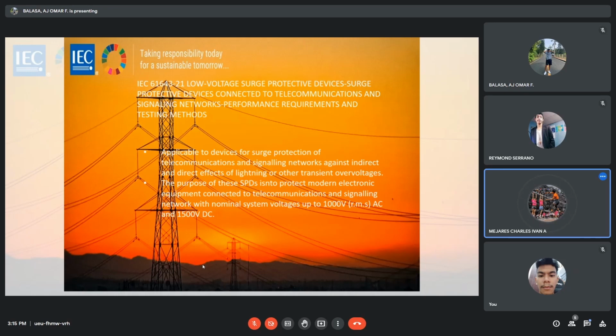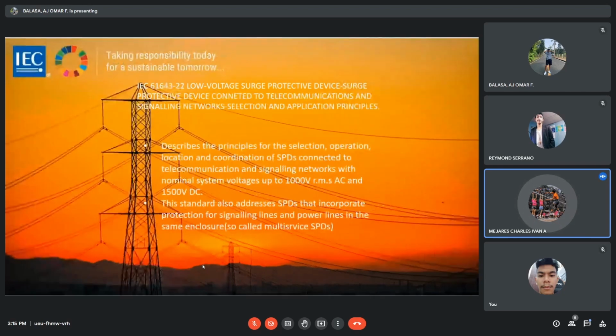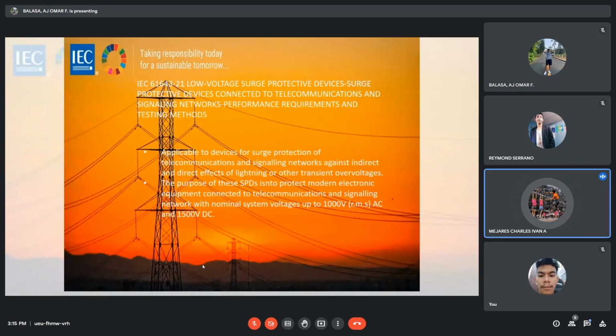IEC 61643-21, low voltage surge protective devices, surge protective devices connected to telecommunications and signaling networks, performance requirements and testing methods. Applicable to devices for surge protection of telecommunications and signaling networks against indirect and direct effects of lightning or other transient voltages. The purpose of these SPDs is to protect modern electronic equipment connected to telecommunications and signaling networks with nominal system voltage up to 1000 volts RMS AC and 1500 volts DC. The SPD configurations described in these standards are composed of one or more voltage limiting components and may include current limiting components. Next.